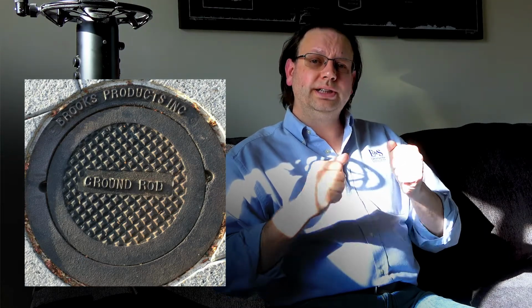So you can only use this in very specific areas, and usually only when you're first in construction, because once that substation is turned on, it's highly unlikely they're going to turn it off again for you to do this test. It's highly unlikely you're going to unbond all of the various bits of wires that are coming in, all of the telco lines and water pipes and everything else that may be feeding that substation that could compromise your test, right? So usually you do this test only in greenfield environments and only as a validation during original construction, and it's almost never done afterwards. What we tend to do is rely on computer models and dedicated test wells to check individual ground rods that are inside of that substation in order to see if those are corroding. And that will tell if one of them is corroding, probably the rest of them are corroding as well.